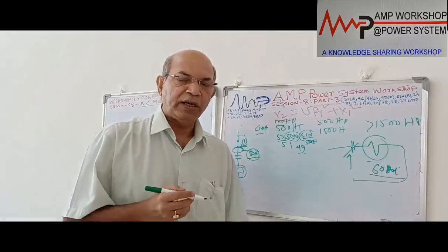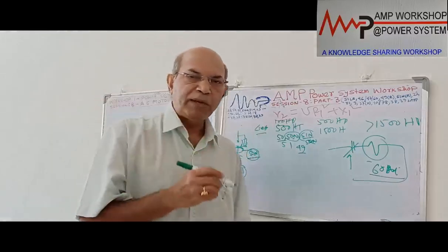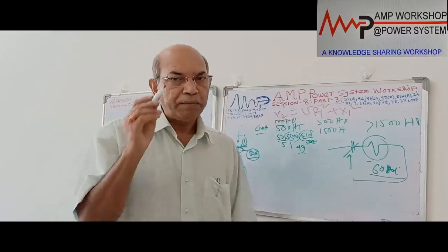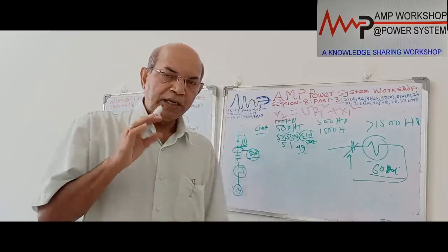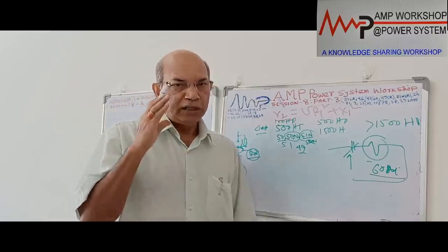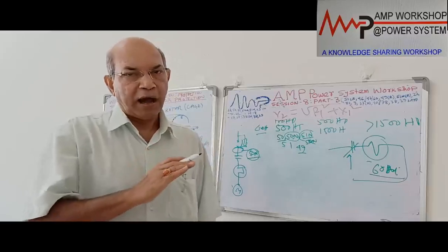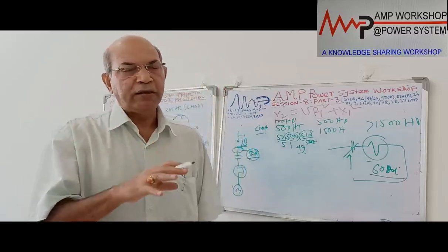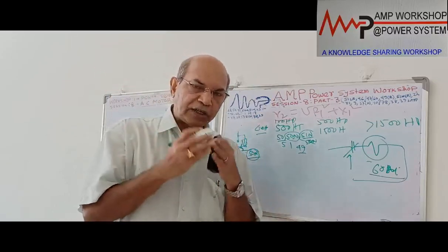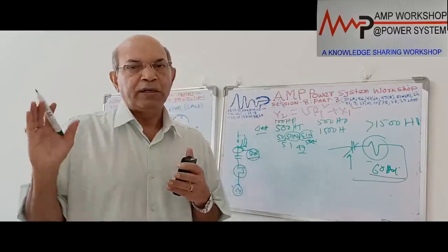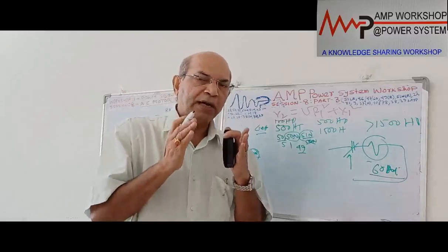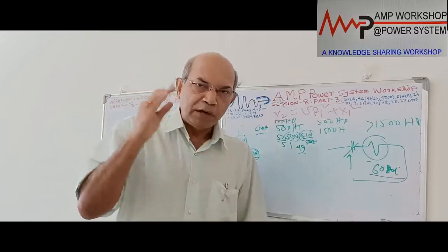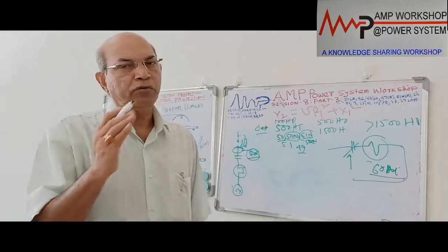But nowadays in a solid state relay, we can program this. The moment we give the start, immediately the relay understands that a start command has come. At that time, it has a memory where it can accumulate how much heat is produced, keep that image, and calculate with the time how much heat has been dissipated. Depending on this generation and loss of heat, the motor relay can calculate the cumulative heat at this moment. When the total cumulative heat value is below the respective withstand time, only then will the motor be allowed a second start.